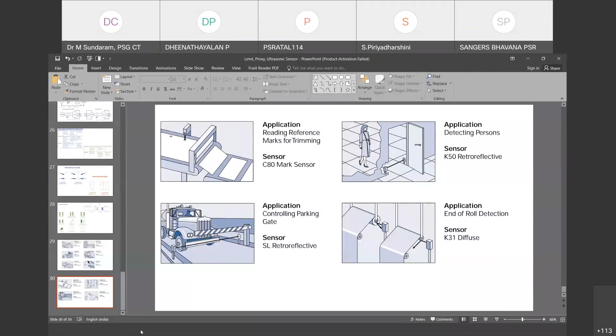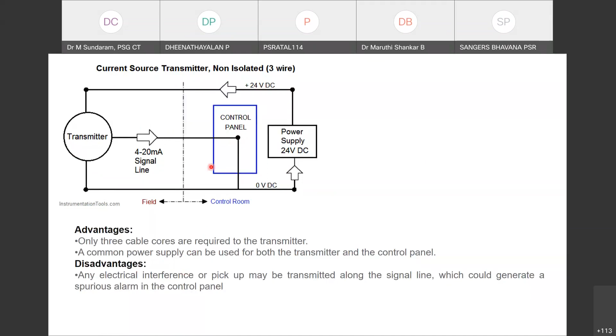That analog may be a 3-wire analog sensor, where plus supply and minus supply is common for transmitter, sensor, and controller. Advantage: minimum wire requirement. Disadvantage: electrical interferences will be picked up. Some small noise generated in the sensing domain will be picked up, so sensitivity is going to be poor.